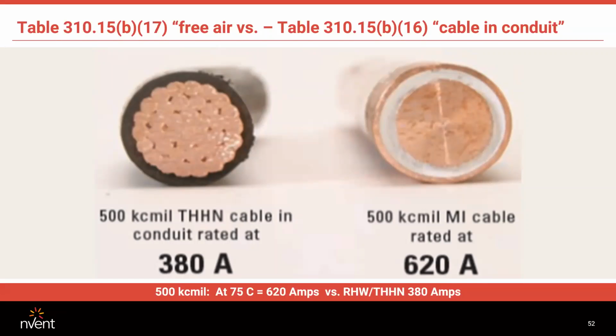Probably what I'd say 70% of the engineers I deal with do is they just spec the same size MI as they would pipe and wire. If they do that, you'll always be covered because you would never need a larger size MI than you would pipe and wire. About 30% like to take advantage of the free air rating. Either or is fine. But again, with the free air rating, be mindful that because you are pushing more current through a cross-sectional area, you will get a bit more voltage drop.